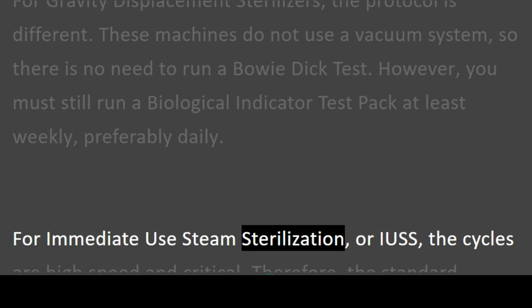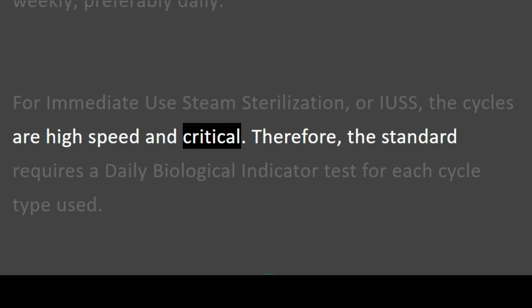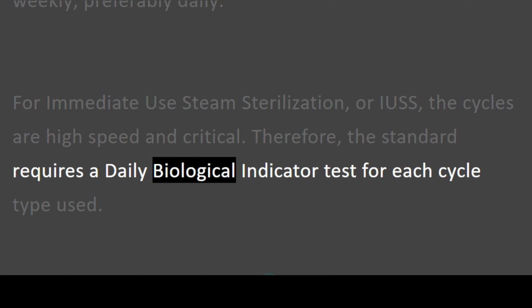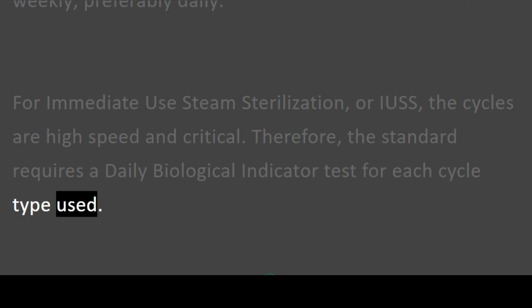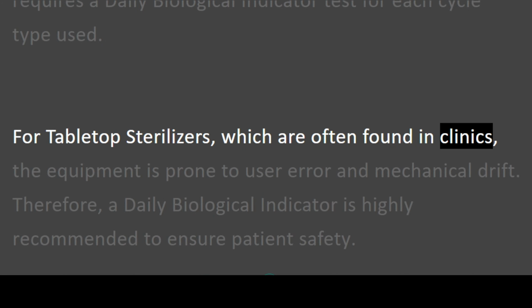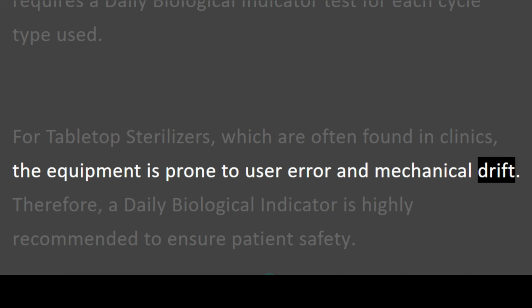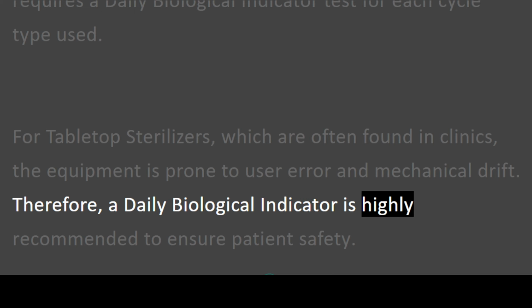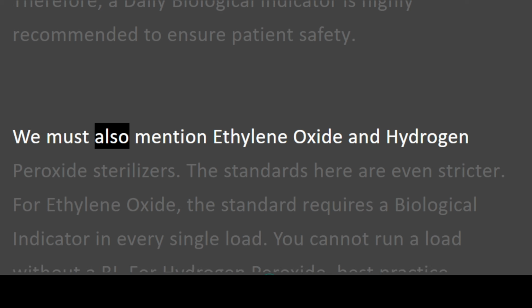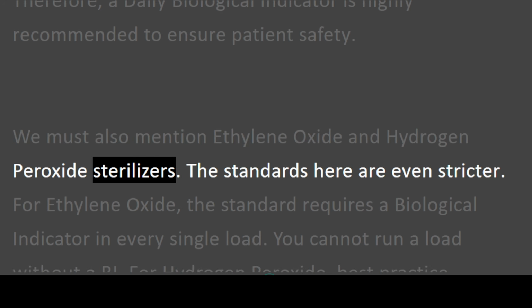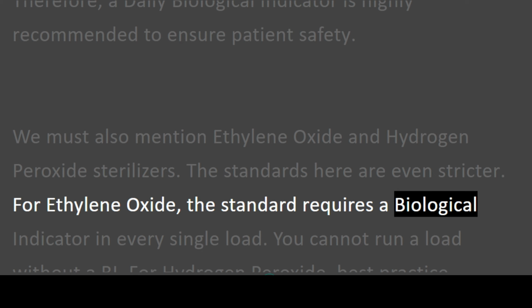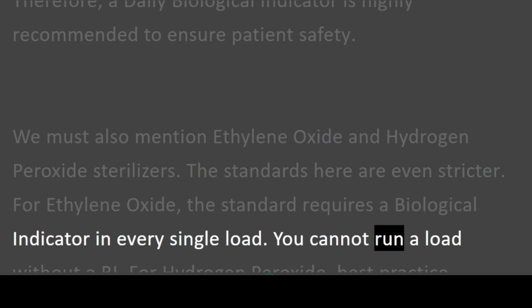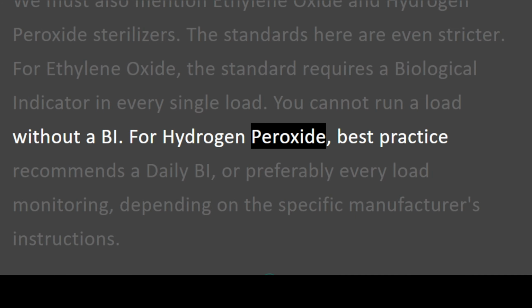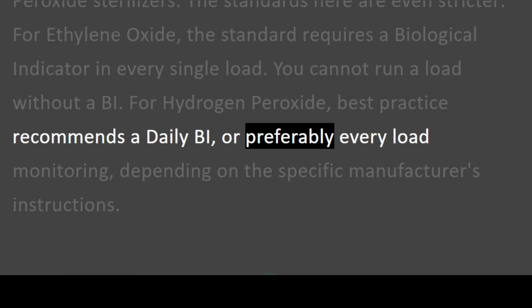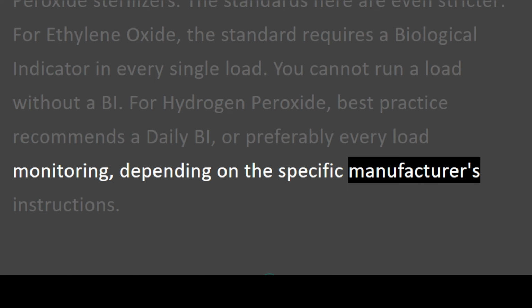For immediate use steam sterilization, or IUSS, the cycles are high speed and critical. Therefore, the standard requires a daily biological indicator test for each cycle type used. For tabletop sterilizers, which are often found in clinics, the equipment is prone to user error and mechanical drift. Therefore, a daily biological indicator is highly recommended to ensure patient safety. We must also mention ethylene oxide and hydrogen peroxide sterilizers. The standards here are even stricter. For ethylene oxide, the standard requires a biological indicator in every single load. You cannot run a load without a BI. For hydrogen peroxide, best practice recommends a daily BI, or preferably every load monitoring, depending on the specific manufacturer's instructions.